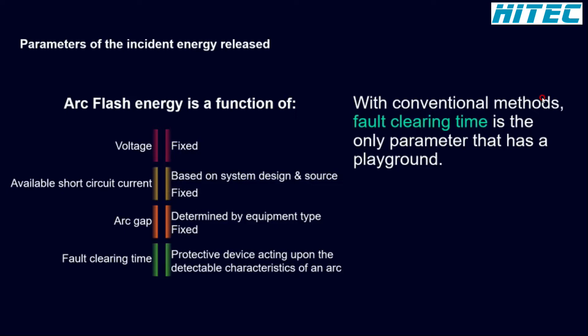Within this dilemma, there are some parameters already fixed without room for adjustment. In regard to limiting the arc flash incident energy, there is also not much room to play. Amongst the parameters, it is the fault clearing time we can act on by utilizing fast tripping circuit breakers and early detection of arc via light or pressure sensors. But what if we would have the chance to act directly on the arc itself?